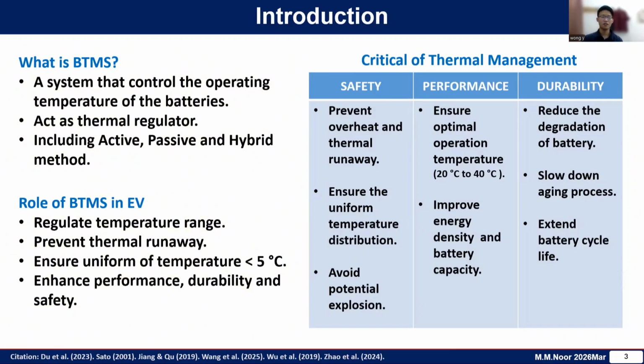The role of BTMS is to regulate the temperature range within the safety range, which is about 20 degrees Celsius to 40 degrees Celsius, and ensure the uniformity of battery temperature is not over 5 degrees Celsius, to prevent thermal runaway. It also can enhance the performance, durability, and safety.